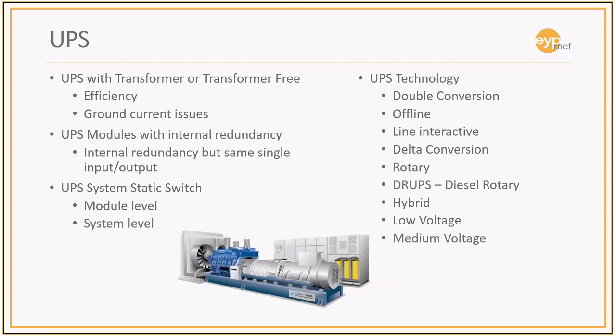But if you're going to go from a lead-acid-based battery to a lithium-ion-based battery, there are other technology changes that have to happen within the UPS. And you need to make sure the UPS vendor is aware that you're changing your battery type so that they can tell you if they're compatible going from one type of system to another.